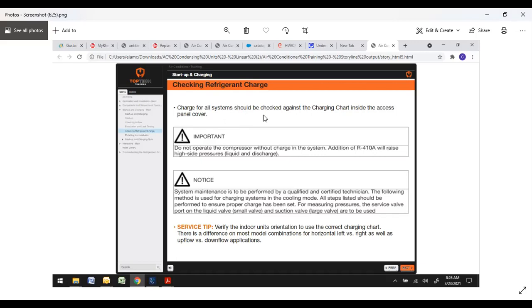So charge for all systems, all the current Rheem platforms. This goes for Rheem, Weather King, Sure Comfort, Ruud. They'll have the charging charts inside the service panel. So that's very important that you use those. Don't just operate on the swag method. Rheem, because you should have matched up to a matched Rheem coil. So if you follow the charging chart, it makes your life a whole lot easier.